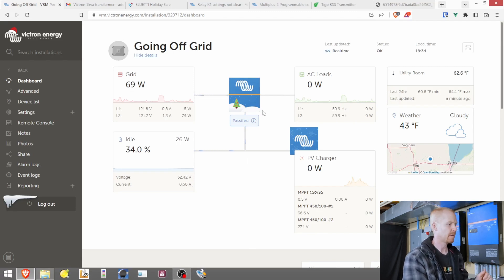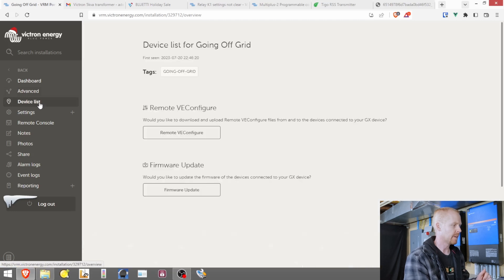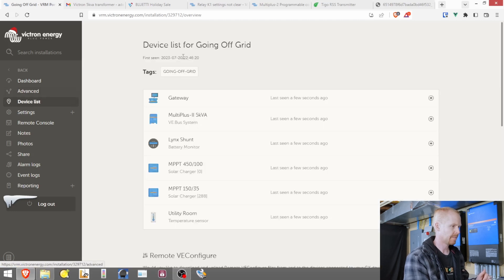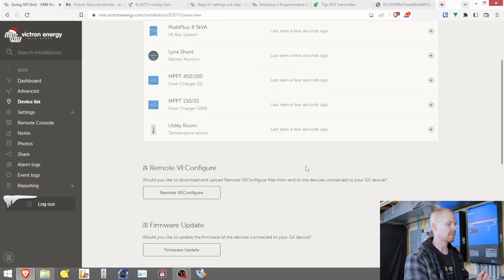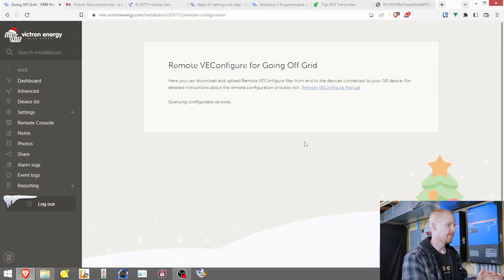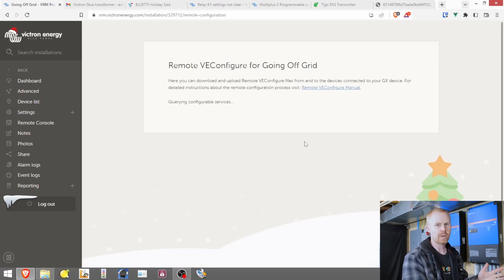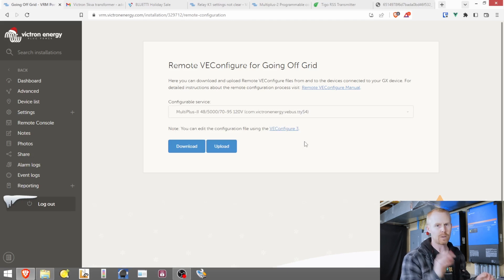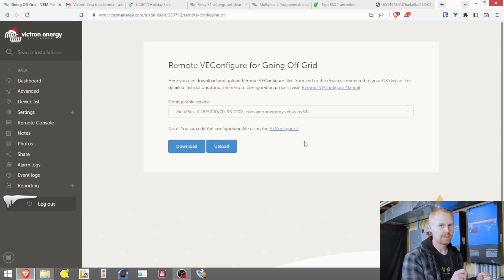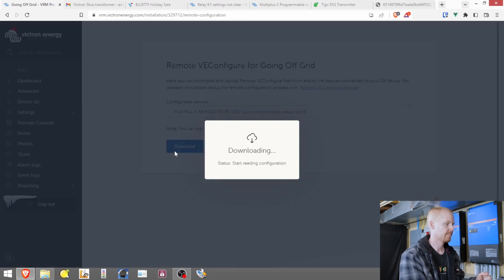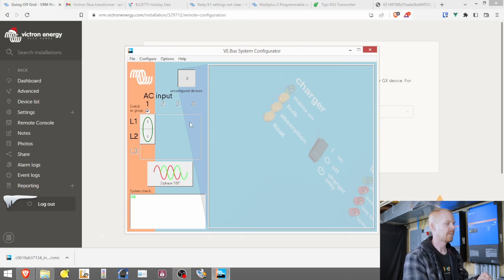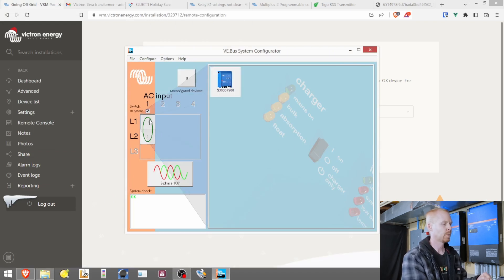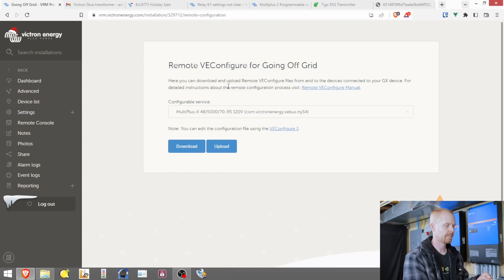We can see that I'm in my VRM. We're in pass-through mode. I'm going to go to my device list. And we need to go to the remote VE configure section. We're going to go through. We're going to get the latest configuration off of the inverters. And then we are going to go through and make one little change and then push that change to the inverters. We'll open up our VE config file. We're going to look at L1 first. So we see our assistant list.